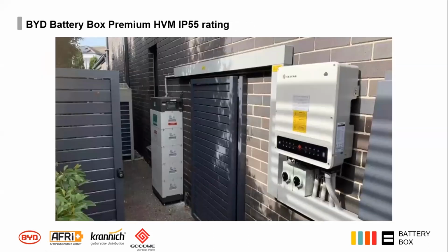And here we have a good example of how an IP55 rating on a system can allow a lot of flexibility where you install. Here we can see a Goodwe high voltage inverter and a BYD high voltage battery bank. And because the entire system is IP55, you can actually install it outside. So when the customer is short on floor space in his house and he asks if the system can please be installed outside, the answer is yes. And almost all of the components are installed outside, including the battery disconnects.